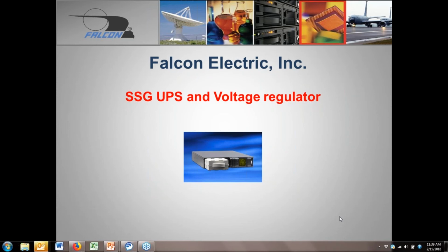So they will require at least a 24-hour run overnight, a minimum of 8 hours to get it to at least 90%. But overall, if you give it 24 hours, you should be okay to get your full battery runtime capacity, especially if you're going to perform testing. A lot of customers like to perform testing out of the box, not really giving the batteries a chance to give the full capacity, and then we shorten some of the runtimes. So we always recommend a good 24-hour charge on the UPS once it's installed before you run any tests. But right out of the box, 8 hours, you should be fine to 90%.